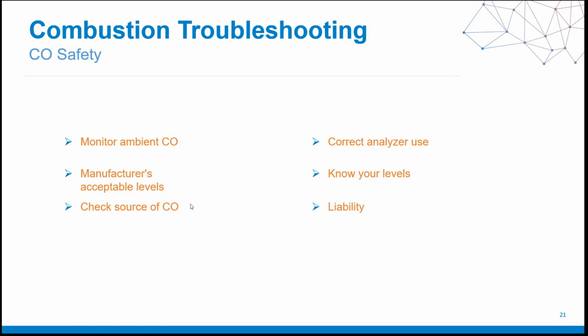We want to make sure that we're following the protocol on how to use an analyzer. And at the fundamental level, that protocol is to start up that analyzer outside in fresh air with no probes or hoses attached. This way it can establish a baseline. And that baseline is going to be 0 CO2, 0 CO, and 20.9% oxygen, because that is the percentage of oxygen in the air that we breathe, as we discussed earlier.